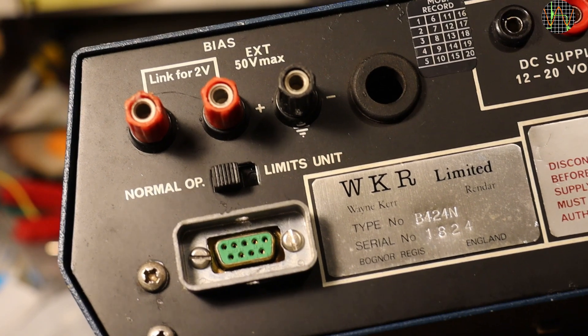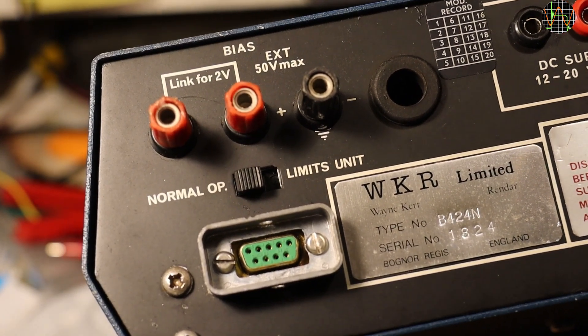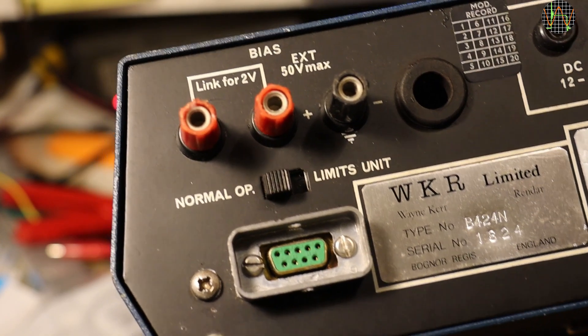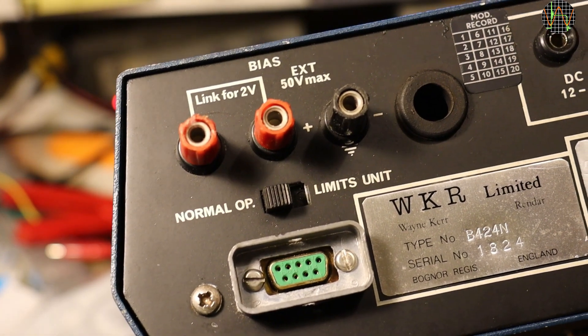On the rear we have connections to add either 2V for internal bias voltage if the two red terminals are bridged, or an external bias voltage between the middle right and the black terminal. Any bias is only applied when measuring capacitors.